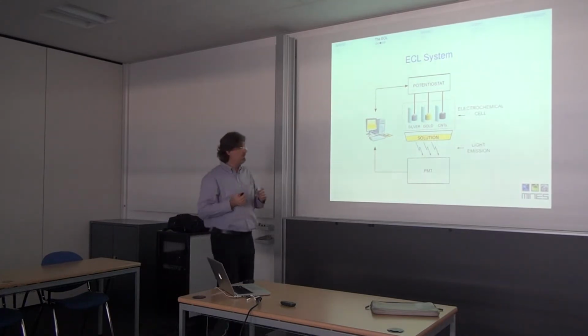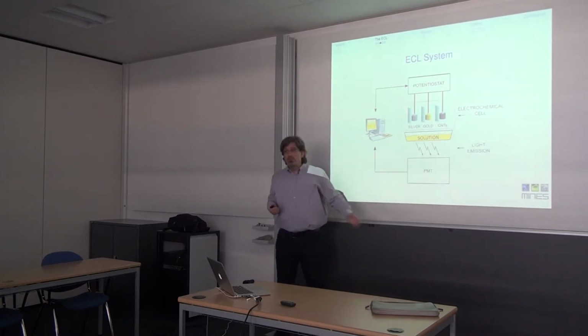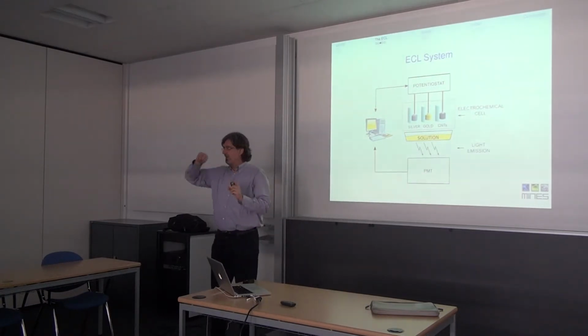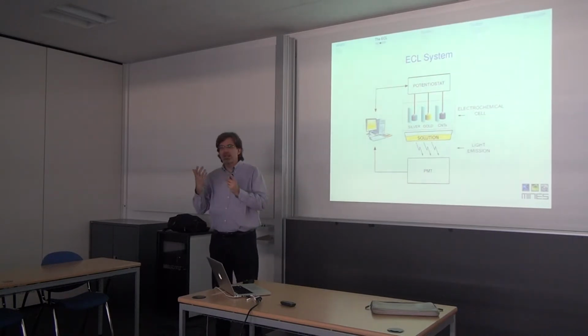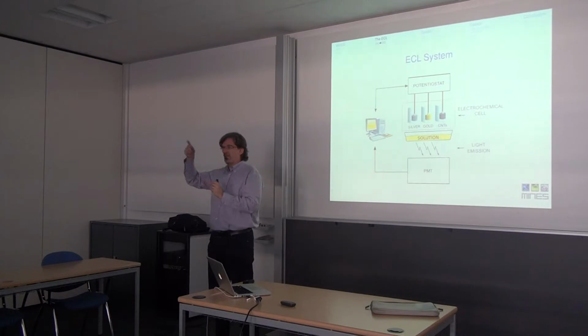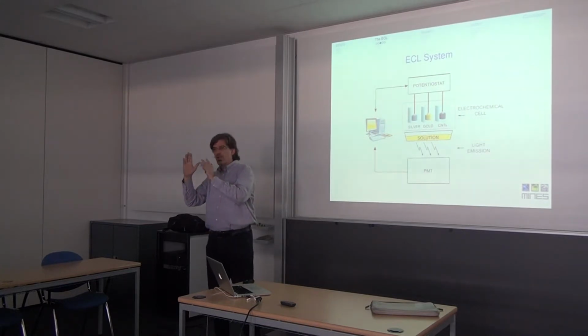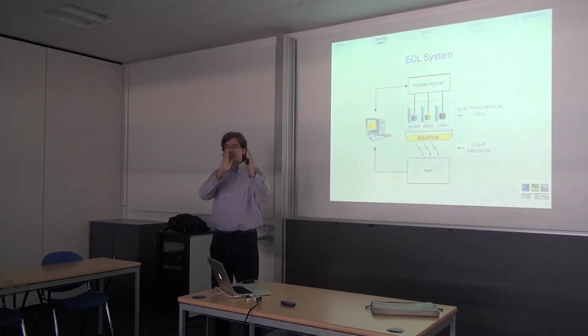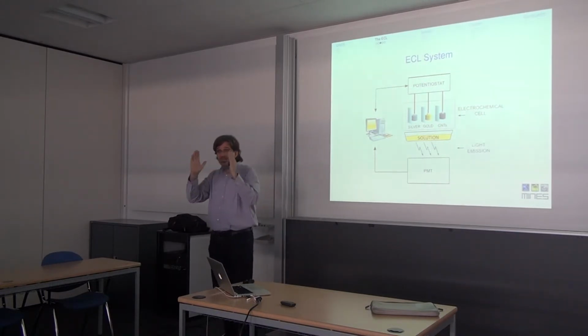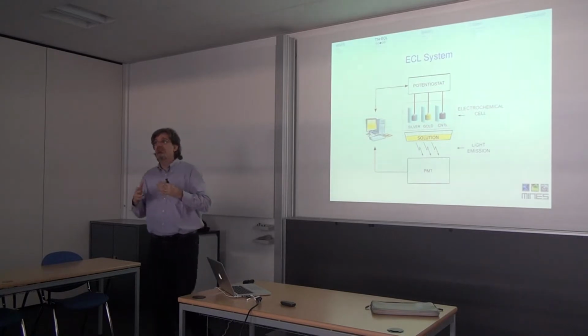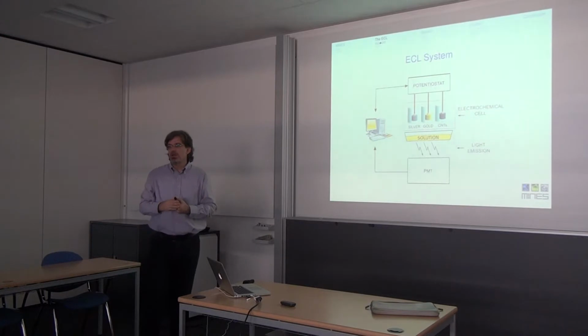In fact, what we did, we bought a photomultiplier. The efficiency of the photodetectors is a sort of Gaussian, no? Depending on the technique and the materials of the photodetector, it can be more efficient at some wavelengths than others. So we chose the best photodetector having the highest possible efficiency in the wavelength we are using.